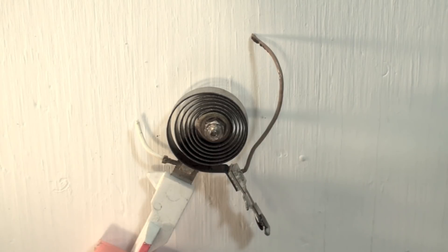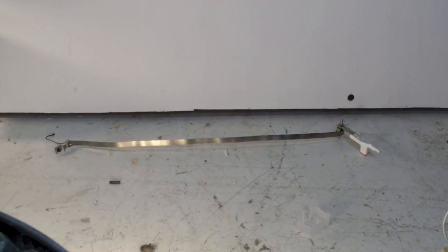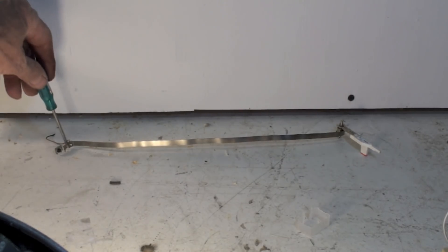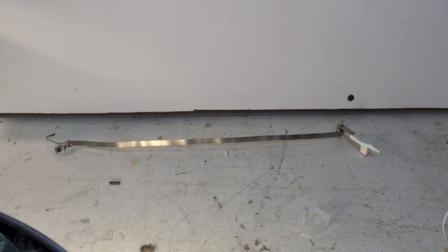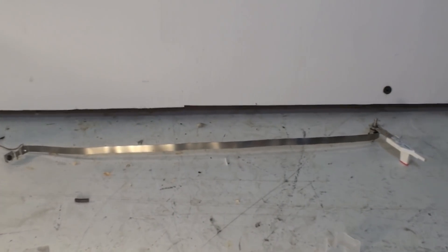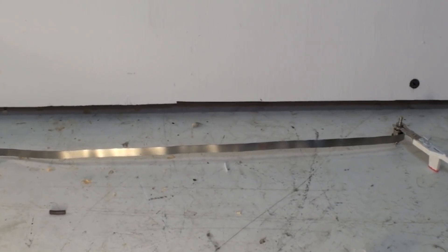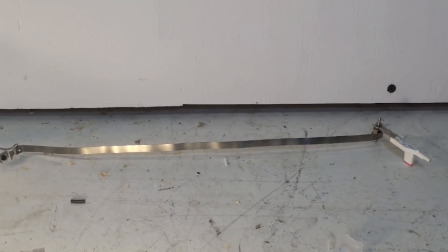Here I've stretched this thing completely out and it's about a foot long from here over to here. That length, obviously I couldn't make a thermostat that was that long. So if I spiral it, that makes the length give me a more accurate reading because it will move more for a given temperature change.